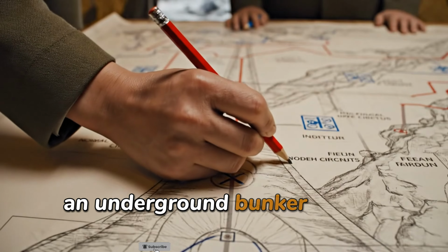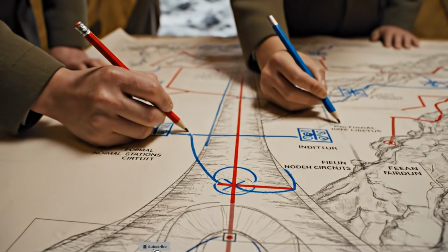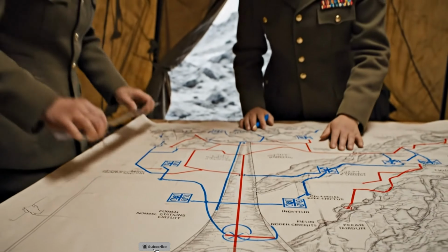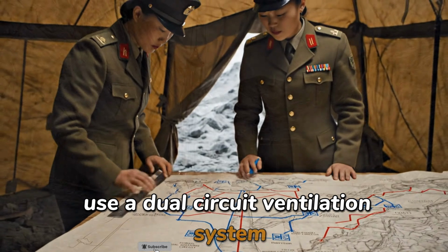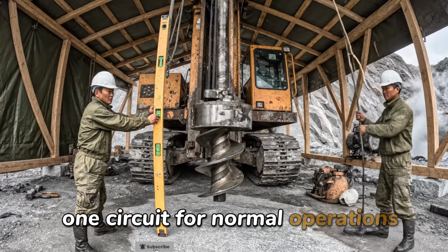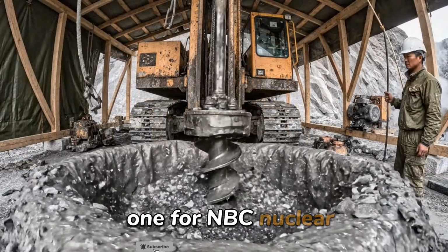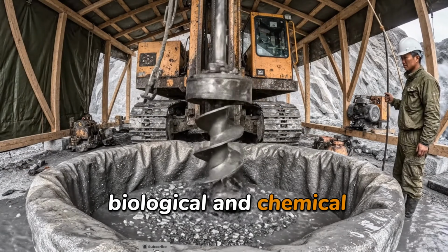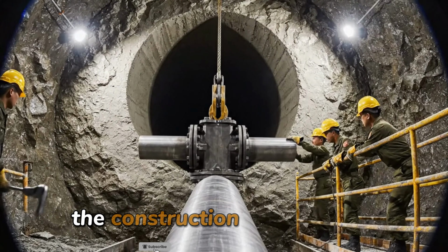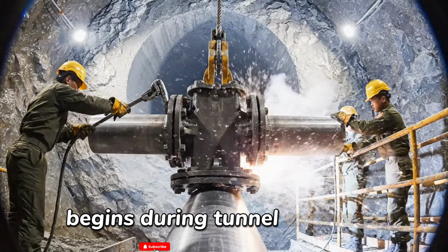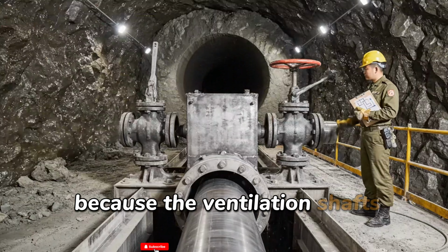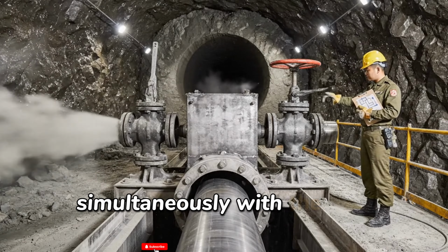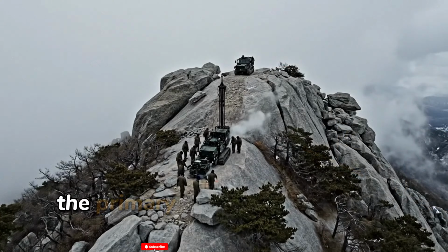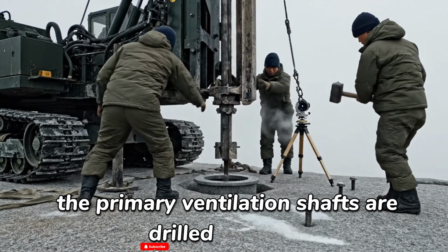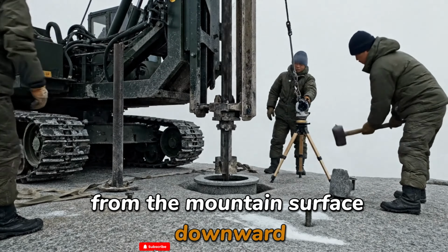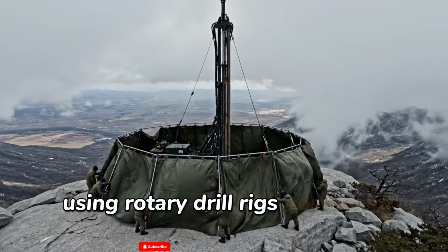An underground bunker with no air supply is a tomb. North Korean military bunkers use a dual-circuit ventilation system. One circuit for normal operations, one for NBC (nuclear, biological, and chemical) contamination scenarios. The construction of this system begins during tunnel excavation because the ventilation shafts must be bored simultaneously with the main tunnels.